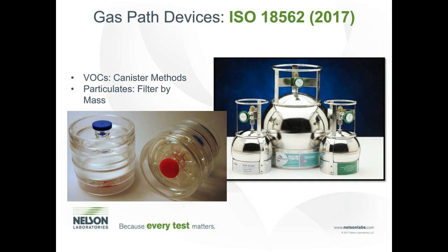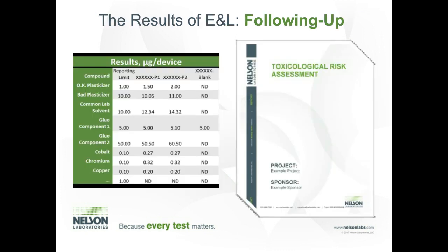these all get summarized into a report, and the results of chemistry testing are like what you see on the left there, where you could have a long list of compounds and how much is in the device. We're seeing more and more now that when folks do chemistry testing, the quality of the results can vary pretty widely. For example, sometimes all of the concentrations are just estimates. Other times, they're rigorously validated, fully quantitative results. We're seeing the FDA more and more really want to see fully quantitative analytical results.